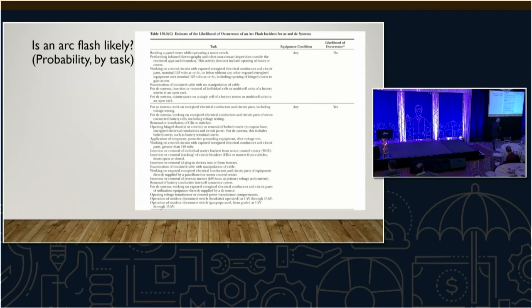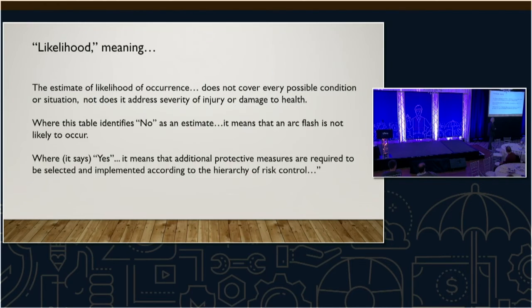The most common case is when people are troubleshooting or voltage testing -- power's on, you've got a meter, trying to figure it out. That's listed right there, even though you can't read it: any type, any condition of equipment, yes, there's a likelihood of arc flash. It happens to be above a certain voltage, but basically there's an arc flash hazard, and we'll leave it at that.